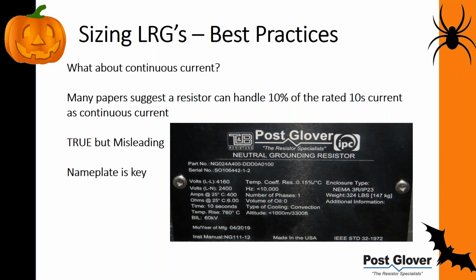But I also think it's kind of misleading, because the goal is not really to operate 10% of the current continuously. The goal should be to operate 10% continuously and then also be able to handle a fault on top of that, because if you have a continuous current flowing, you obviously have a continuous temperature rating that's higher than ambient, and you're going to be adding to that when you have a fault. That can be an issue, and you need to take that into consideration. I think there's sometimes when that doesn't happen. That's a worry to me.